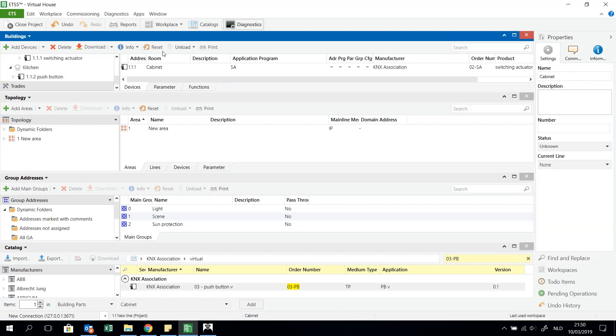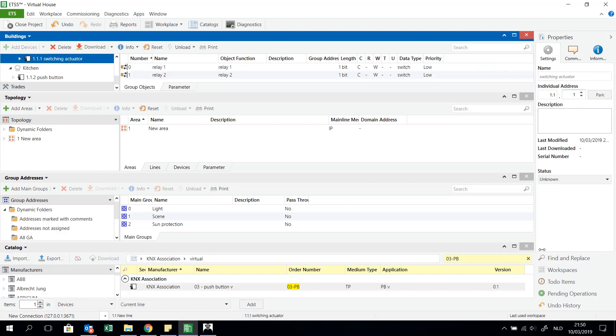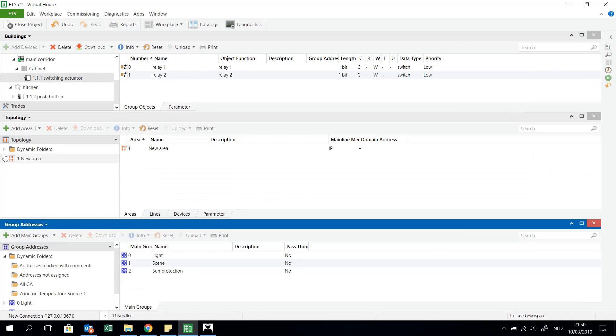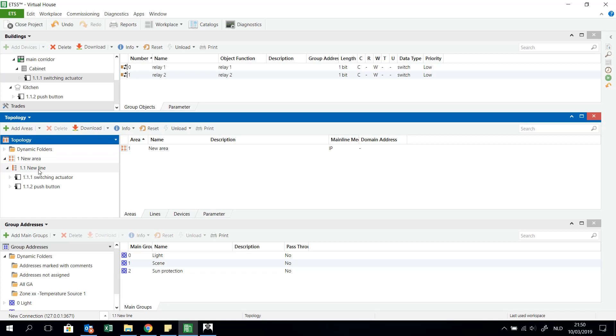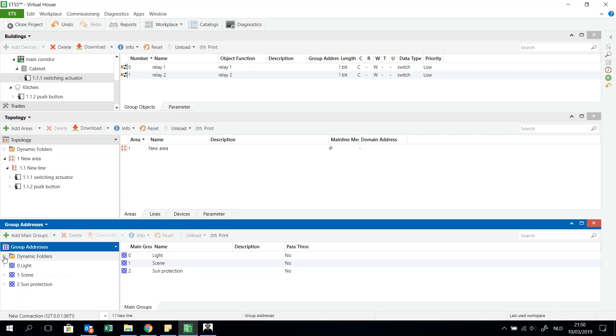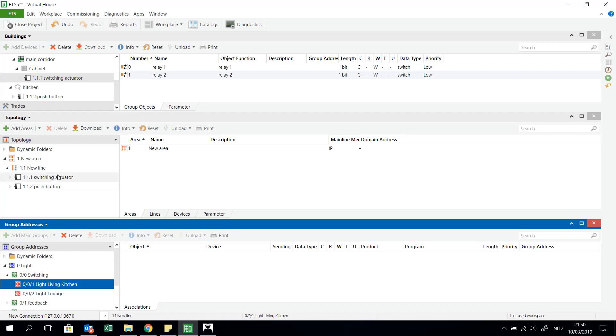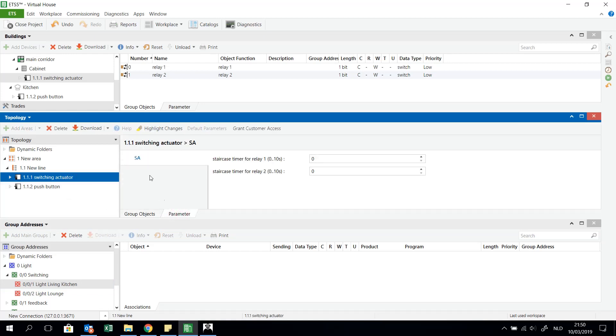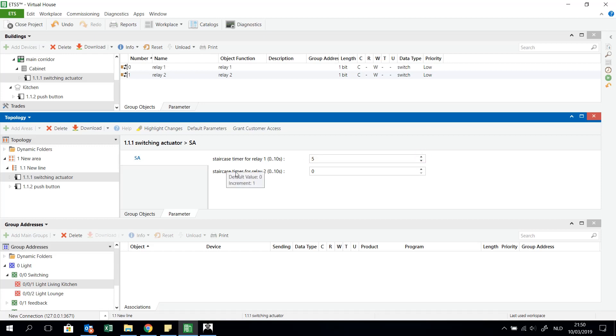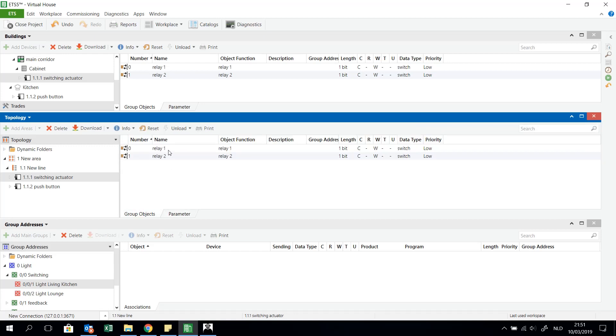You can always change these addresses if you want. I will close some windows. In my topology I created one new area, one new line, and I already have my two components — the switch actuator and my push button. Next I have to connect the objects of this actuator and sensor. In the parameters of the switch actuator I have one parameter for relay 1, which indicates how long it takes to switch off the light connected to relay 1. I can do the same for relay 2, so I only have two objects for this first test.